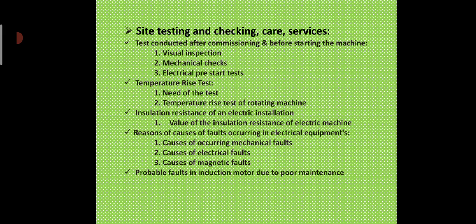Now, causes of magnetic faults. Causes of shorting of the armature core include excessive vibrations, over magnetization, use of improper tools during maintenance, carelessness, etc. Causes of improper fitting of poles with the frame or yoke include improper fitting of poles, avoiding the washer while fitting, less pressure, and excessive vibrations.